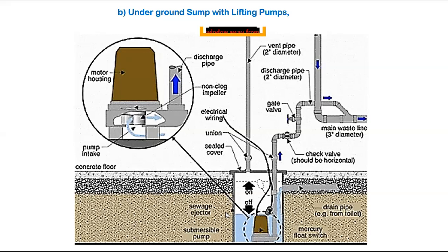So like that you have to put it. This is the typical arrangement. In this pit we have provided one vent pipe also. All the drainage pits will have a vent pipe arrangement. Then only our pump will work without air locking. Otherwise, if you do not provide any venting arrangement, our pump will get airlock, so our discharge will not come. The pumping system also will collapse. That's why you have to provide a venting arrangement.